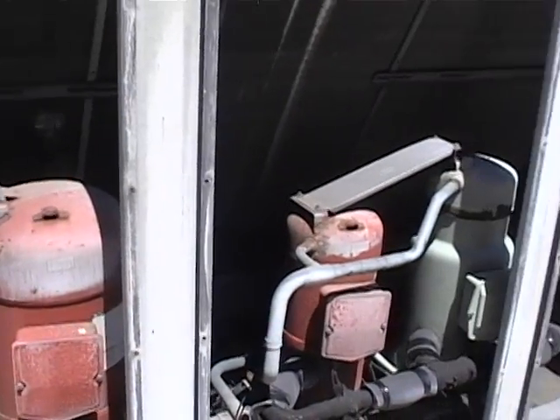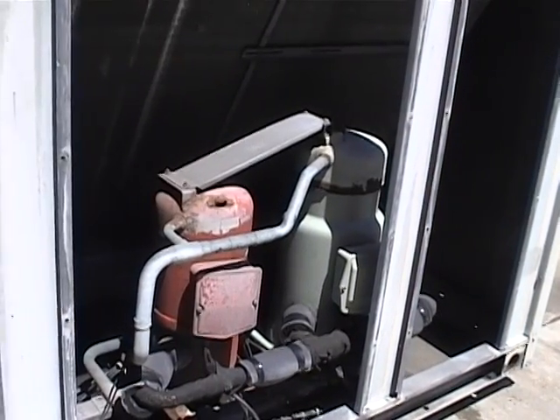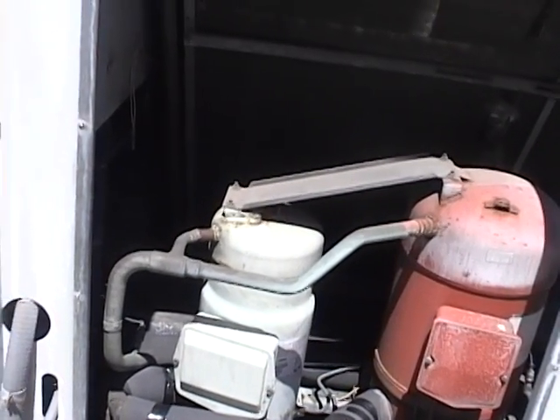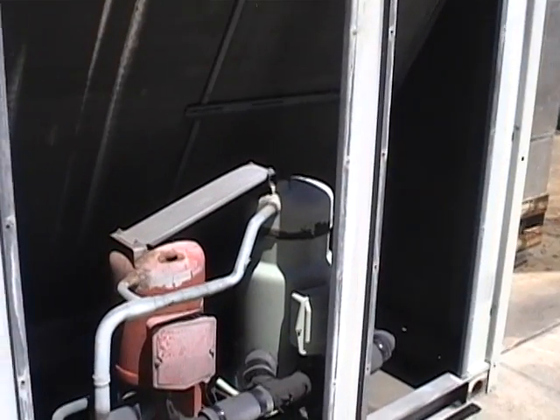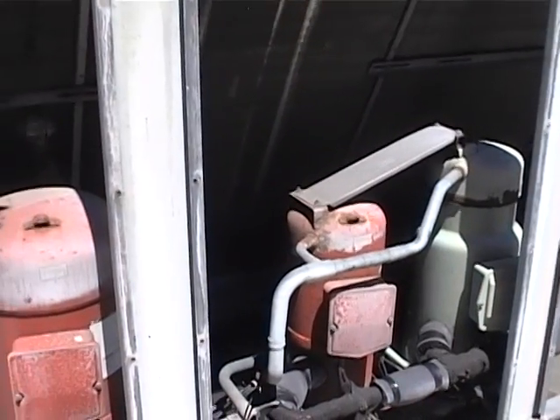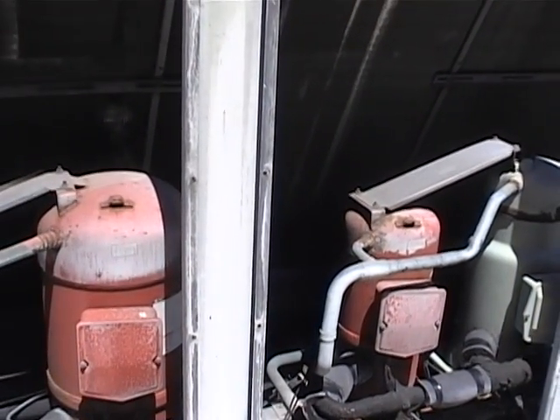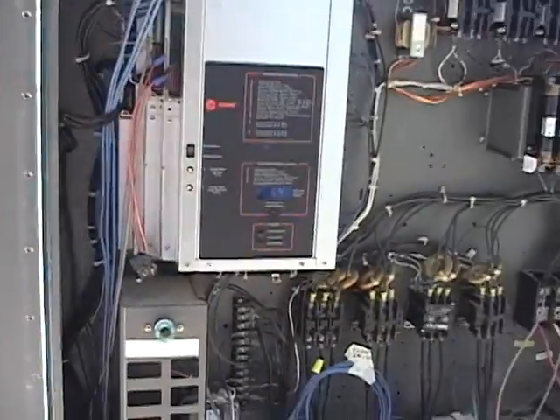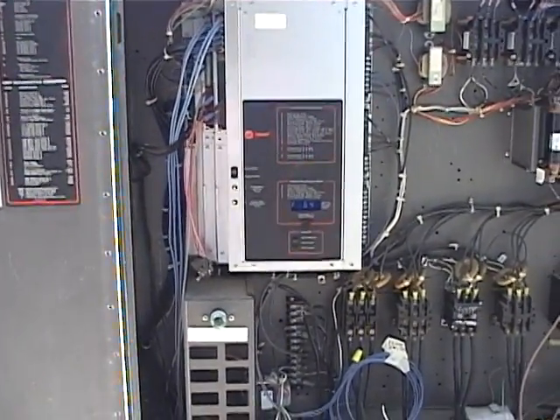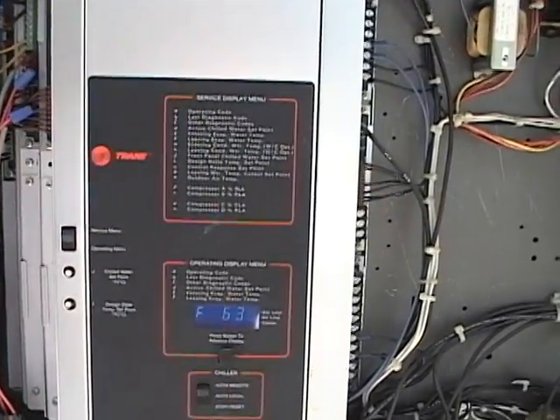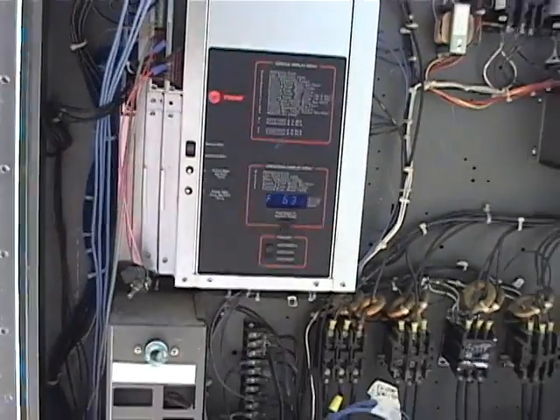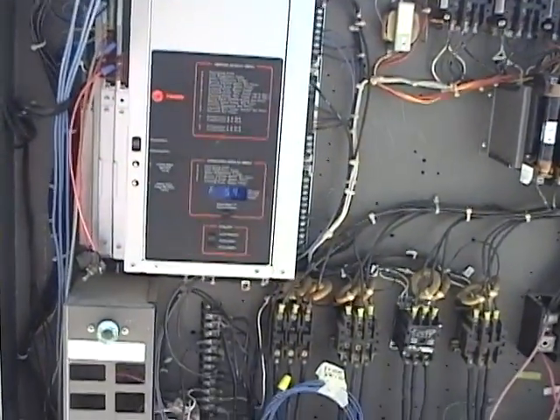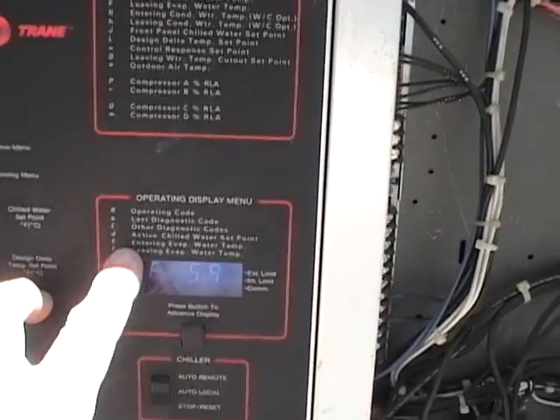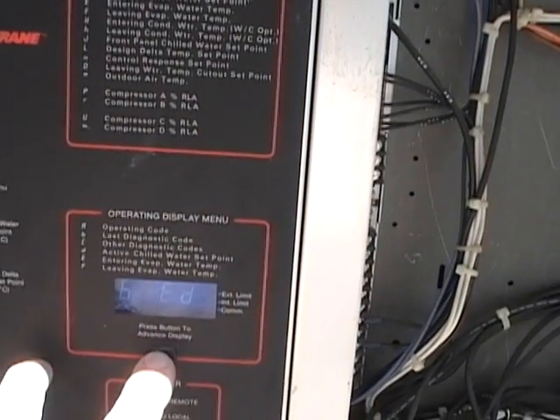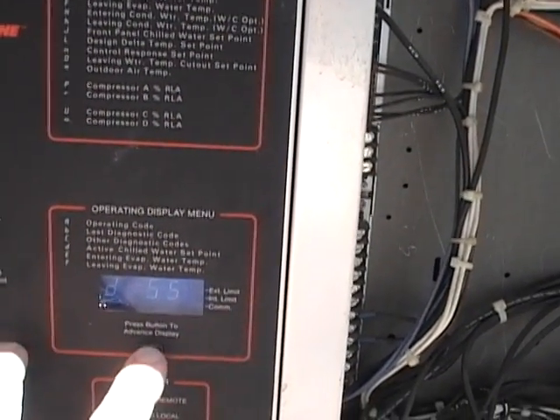Here you can see your compressors running quite well. Nobody making any funny noises. Everything seems to be just fine. And now our incoming temperature is 64 degrees. 63 now, it dropped another degree. Water continues to drop. We are now down to 59 degrees exiting temperature. Of course, our F is the leaving temperature. 55 is our set point.